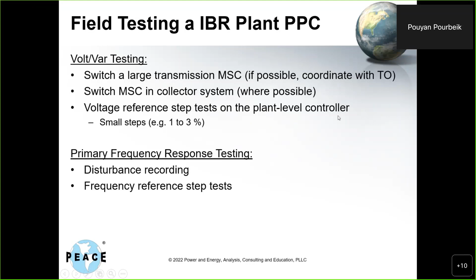Then we go into a field test and ask: can we now verify that the plant model responds the same way as the actual equipment response in the field at the POI, for a volt-var test and a primary frequency test? There are multiple ways you could do this - with voltage reference or frequency reference step tests, or by switching a large cap bank somewhere close to the point of interconnection to cause a fictitious voltage change at the POI. And you could do it with disturbance monitoring, like we said, post-commissioning.